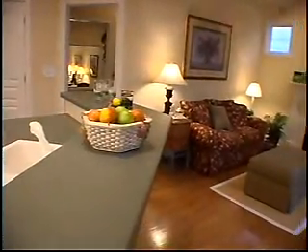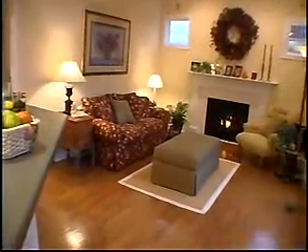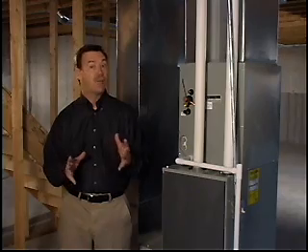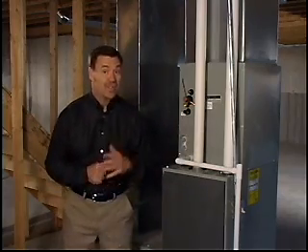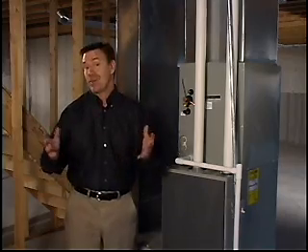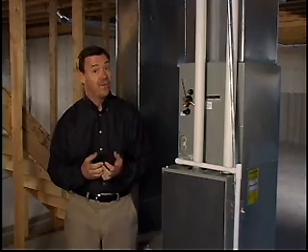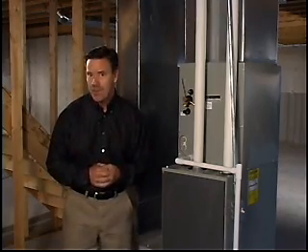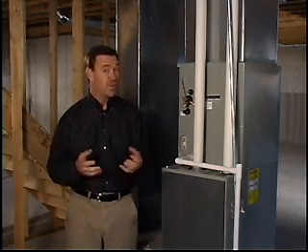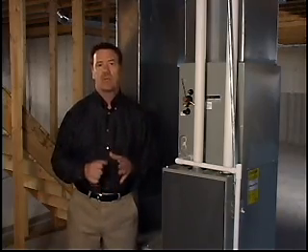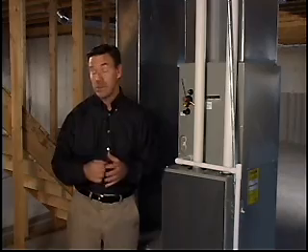Now, how does that relate to a moisture problem? Well, if the upstairs is under a negative pressure, that means that this pressure imbalance is pulling hot, humid air, say for example in the summer when it's 90 degrees outside and 95% relative humidity, into the wall system where it can condense on the backside of polyethylene vapor barriers, run down the wall, and then be absorbed into wood-based building components and create mold-related problems. So it's really important that we seal our ductwork up.